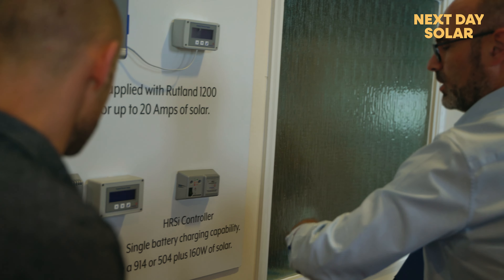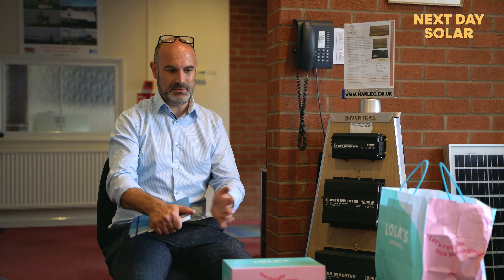If a customer comes to us with a power requirement — wanting to run kit in the middle of nowhere — we'll do the solar side and add a wind turbine. We would always be fairly conservative, basing that wind turbine to produce around 20 ampere hours per day into the battery at 12 volts. That would be on a four to six meter tower with nothing around it — no trees. If it's on a barn or shed, you want to get it two, three, four meters above the roof. The higher it is, the clearer the wind and the more output you'll see.